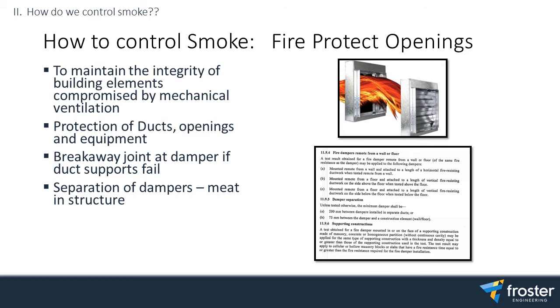I need access to get to that damper. That duct is already small as it is. It's physically impossible to provide a proper fire damper that has access. So to do it properly, I've got to open up my ductwork to get into that riser, so I can fit an access panel in the duct, so that I can actually get to it, and I can maintain it. But that doesn't really happen. I've seen so many examples where that's simply not done. And I'll show you photos of where that's not done.